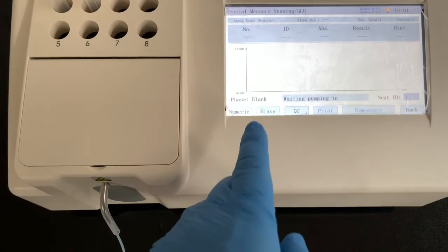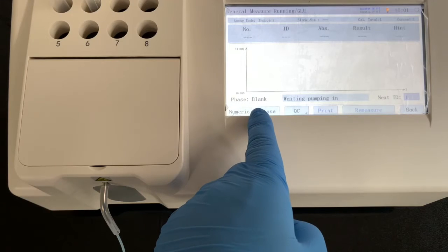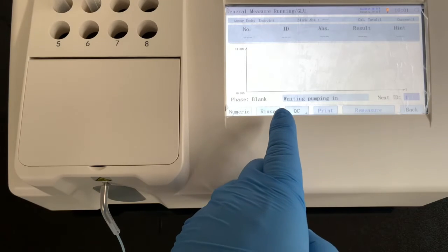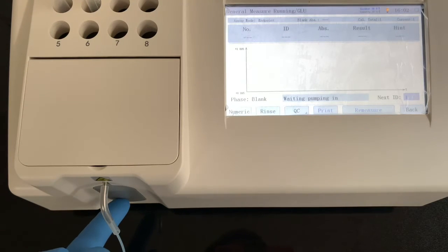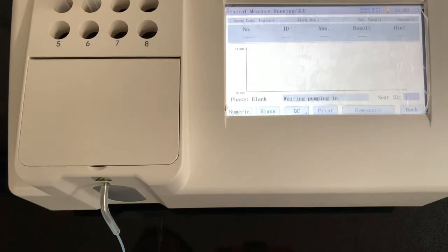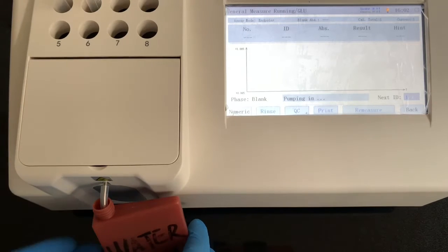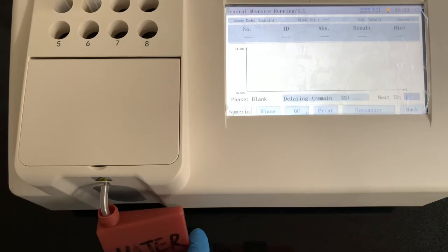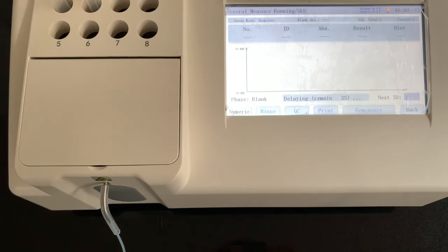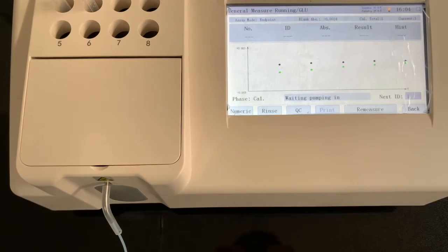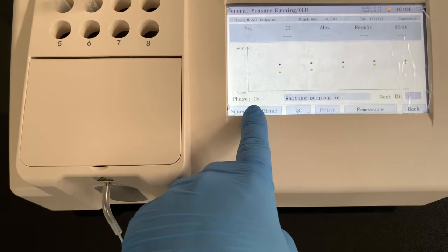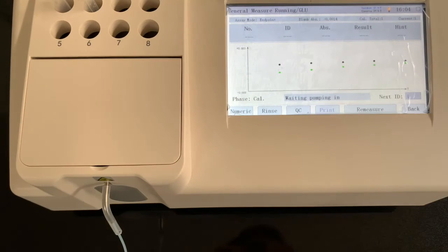In the test menu, we can see the phase is blank. We will give water to analyzer and press the gray Run button to run the blank test. After 5 seconds of delay, analyzer will read the blank and report the blank result. Now we can see the phase is showing cal. Now analyzer is waiting for calibrator pumping in.